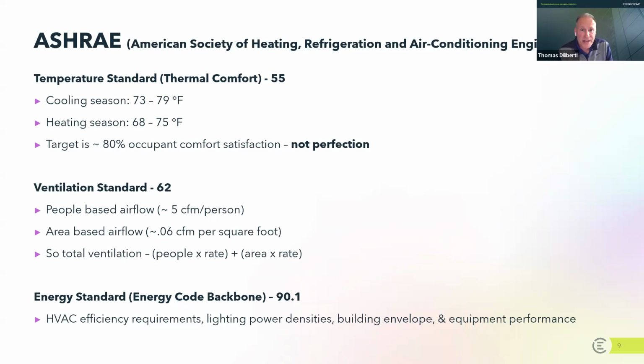ASHRAE also has a ventilation standard. So this is ASHRAE 62. And how ASHRAE defines this standard is they define it based on the occupants within the space or on area or both. And so talking through each of these three bullets, as mechanical teams schedule their systems and they put the values in all of the sensors and the controls in order to manage a system, what ASHRAE 62 says, if you're looking at a people-based airflow, that you should provide 5 cubic feet per minute of air per person in order to have adequate ventilation.